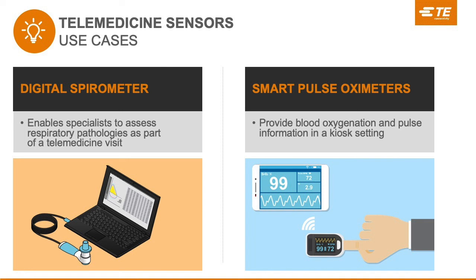Respiratory flow can be accurately measured using differential pressure sensors. The patient's breath flows through a laminar flow element or a screen with a very small flow resistance. A minimal pressure drop results over the element, this representing a measure for the respiratory flow rate or the respiratory volume per time. These differential pressures can be logged with a highly accurate sensor and converted into an electrical signal. The nose clip is typically used to improve the accuracy of the measurements, and special software guides the user through the process and helps ensure the patient is using the spirometer correctly.